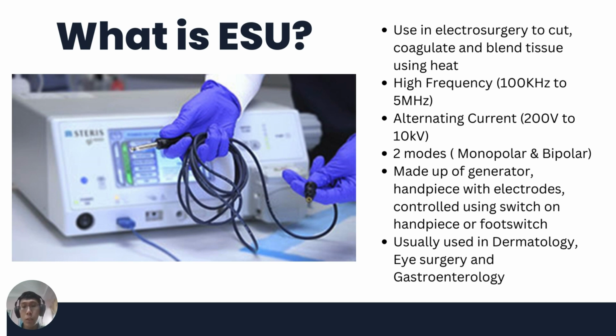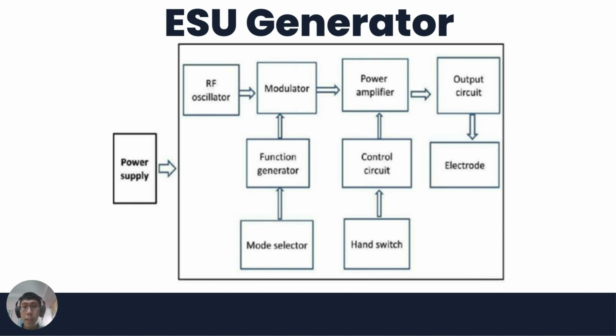An electrosurgical unit is made of a generator and a handpiece with electrodes. It's controlled using a switch on the handpiece or a foot switch. Electrosurgical units are usually used in eye surgery, gastroenterology, dermatology, and more. Electrosurgical units have two modes, monopolar and bipolar mode. The electrosurgical unit is made out of few components as shown in this image.